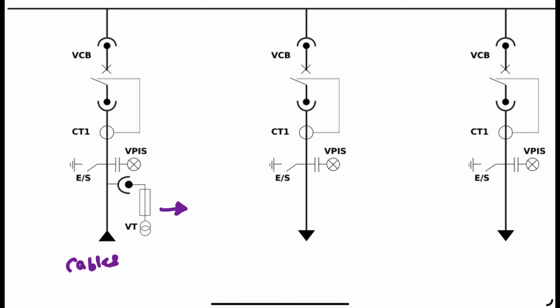So this is a voltage transformer with a switch and withdrawable-type capability. Moving on, we have a VPIS system — Voltage Presence Indication System. This tells us whether there is supply in the panel or not. If we want to carry out maintenance, we need to be 100% sure the supply is turned off, as human safety is paramount. This VPIS system helps us know that.